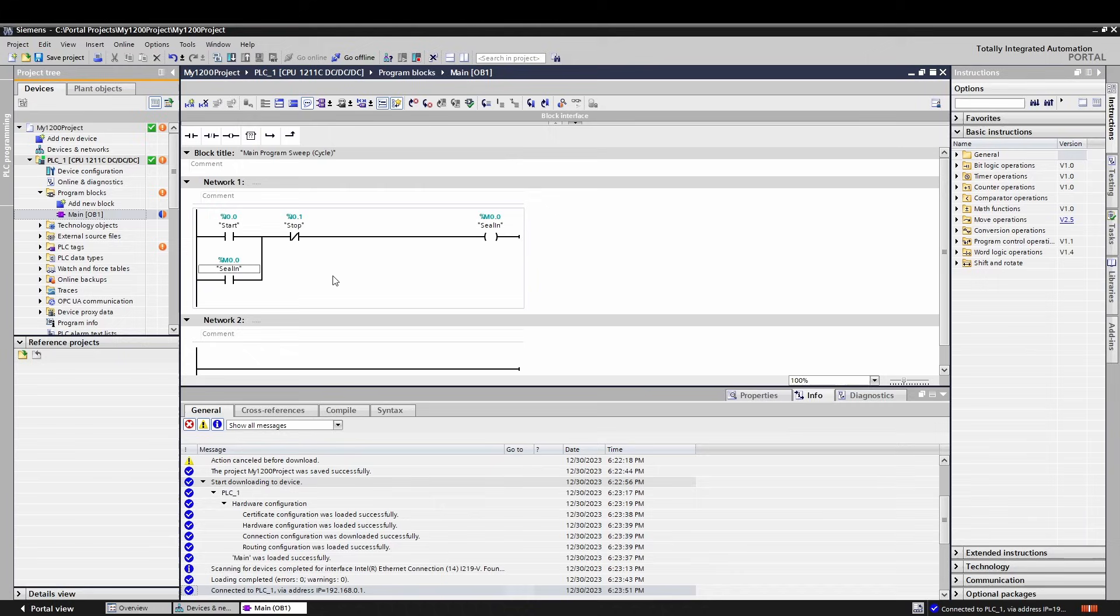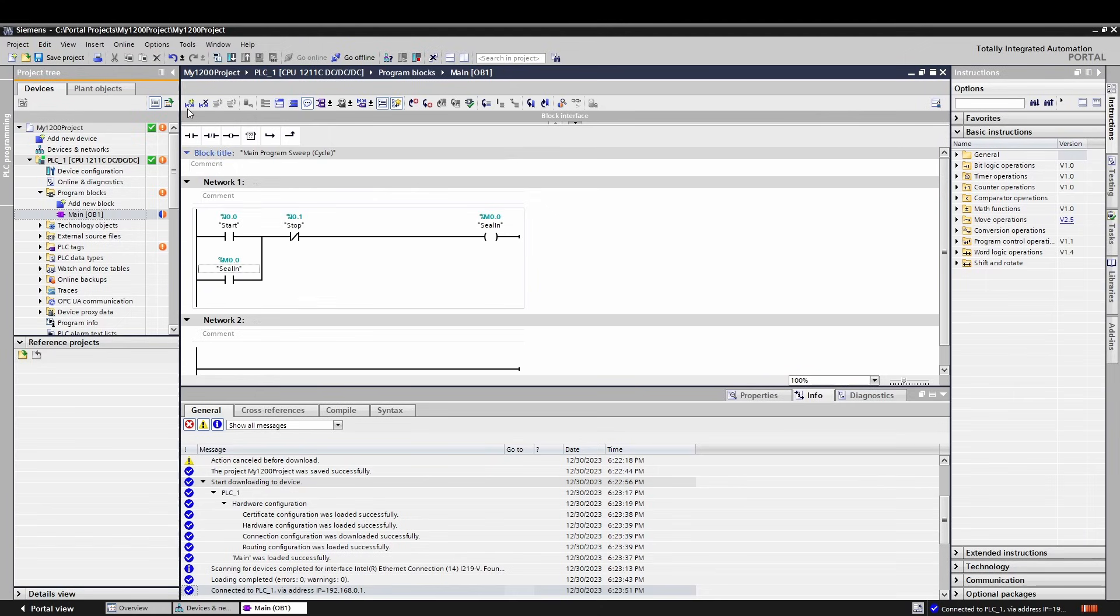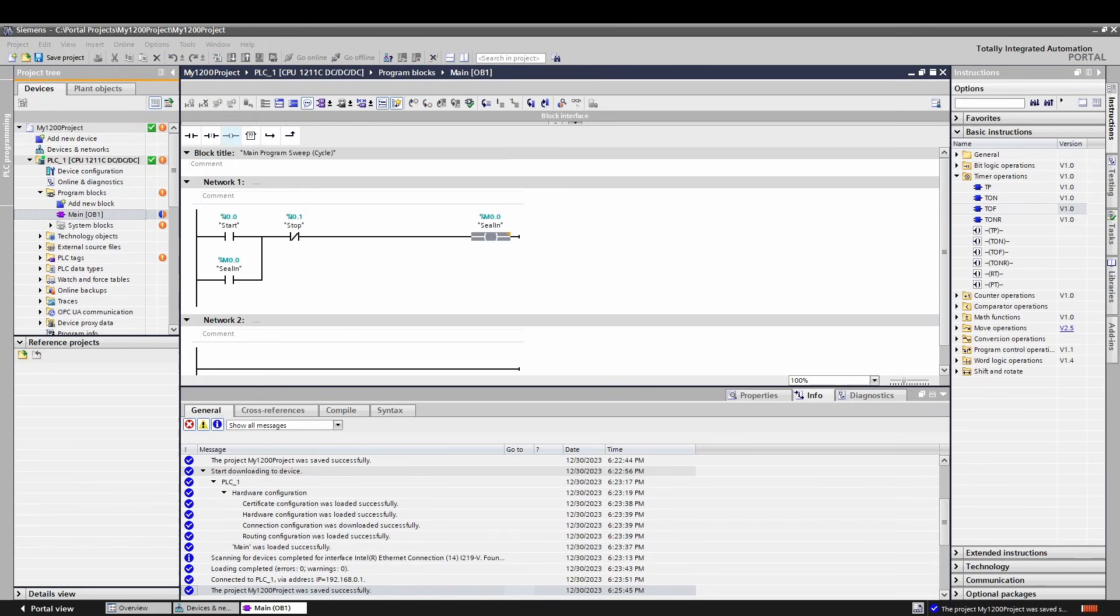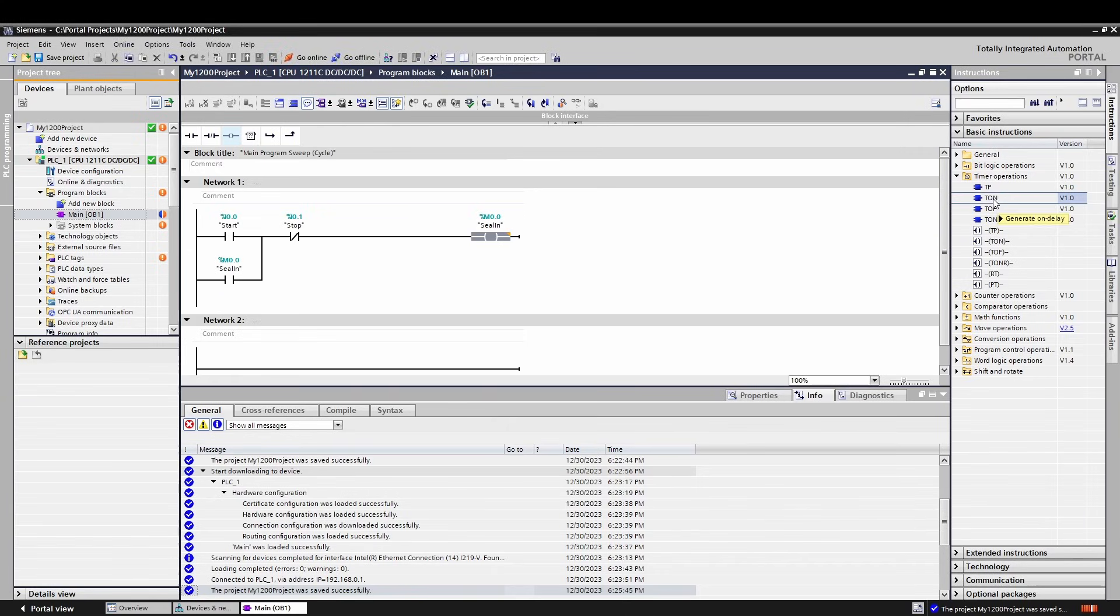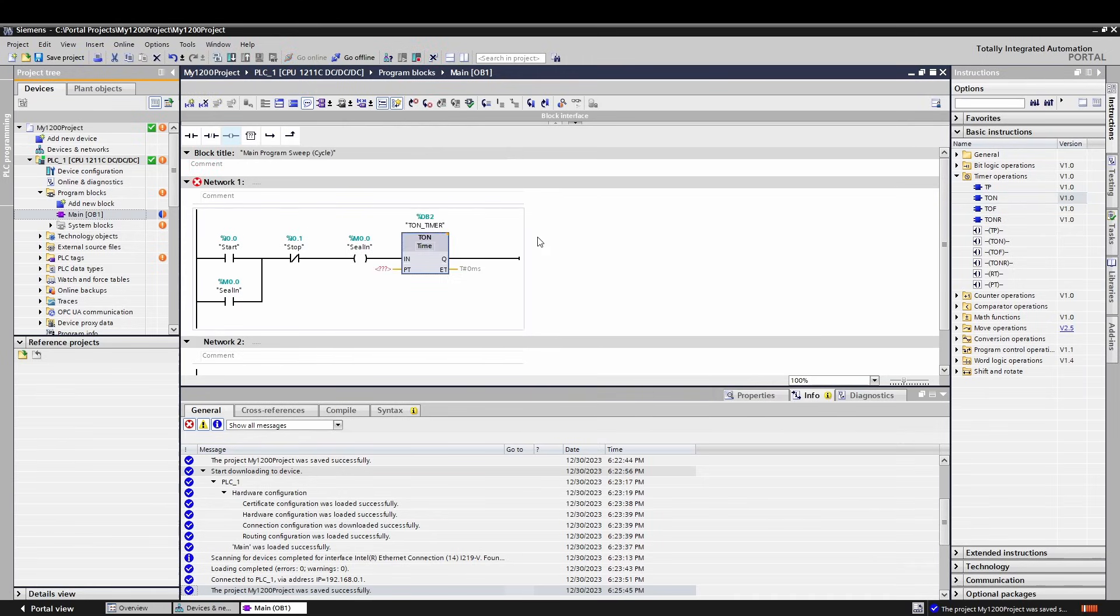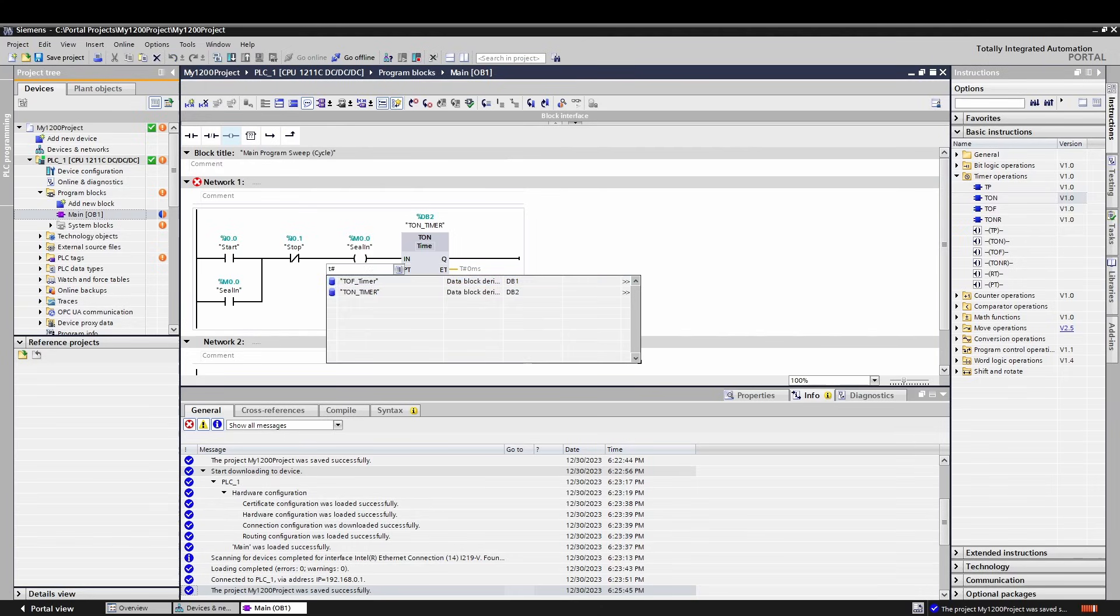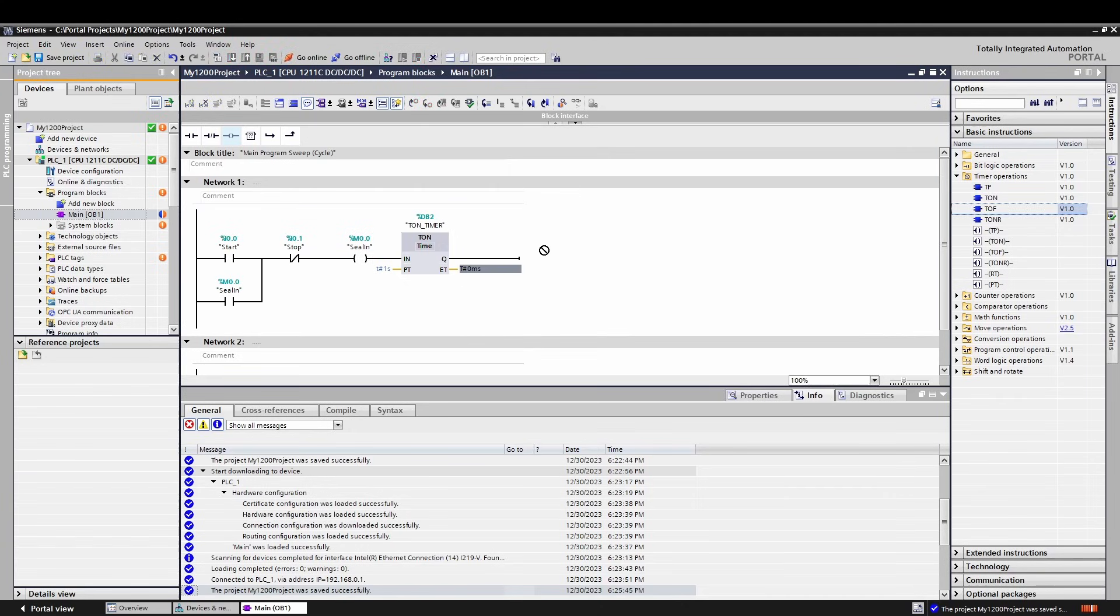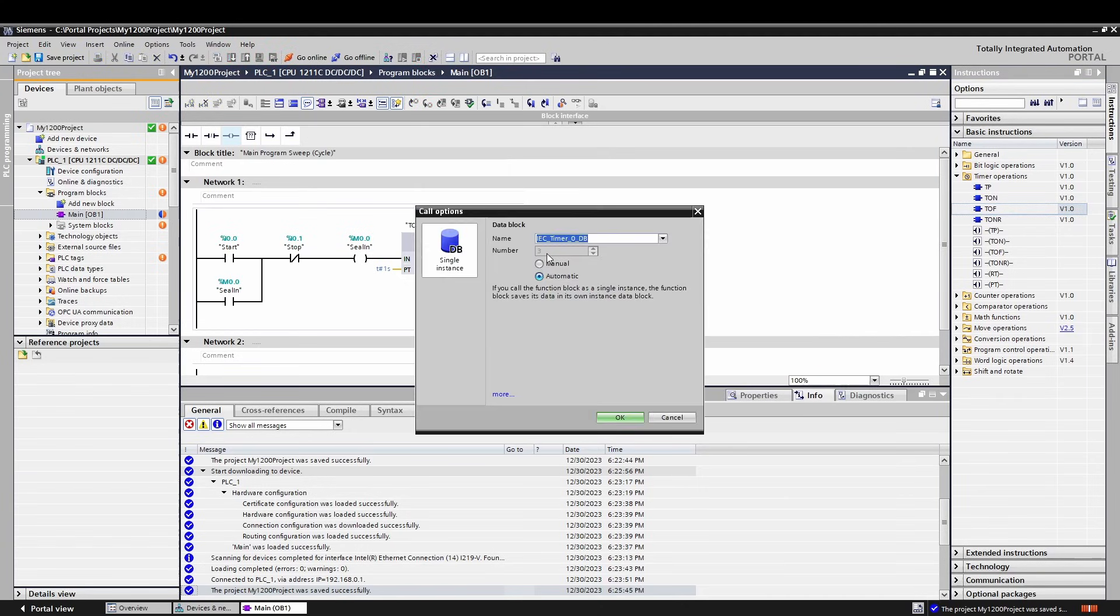We normally now would put our timers on the next line, but I told you we were going to do this on one line. Yeah, I've been told this looks cursed, but it works and it shows the flexibility of the editor. Let's bring in a TON timer from our Timer Operations instructions. This is an IEC timer and requires what is called an instance DB to use. Get in the habit of naming these something that makes sense, as it will save you a headache in the long run. This timer will come on after the input stays on for the time here at the input. We want our output to delay one second before coming on, so let's put in one second here by typing in T#1s.